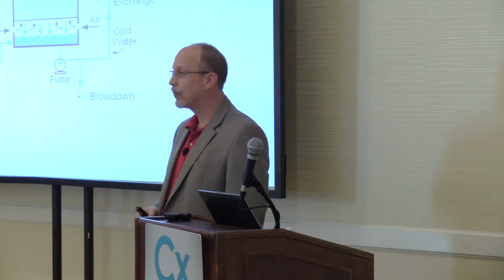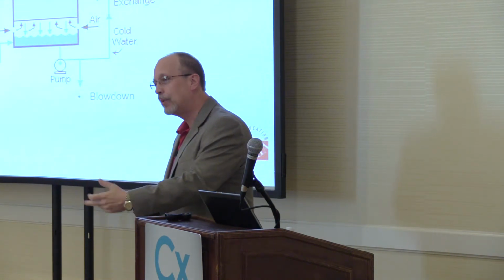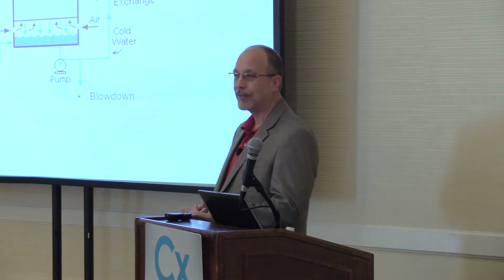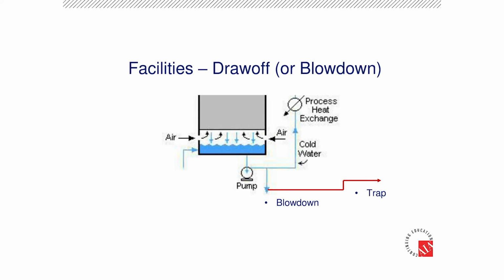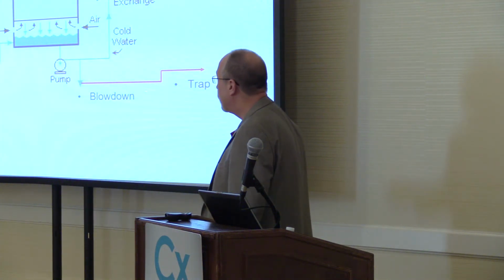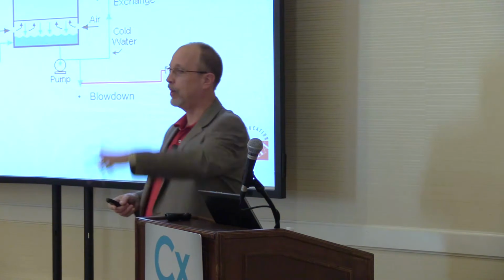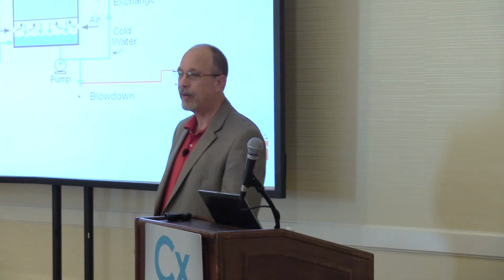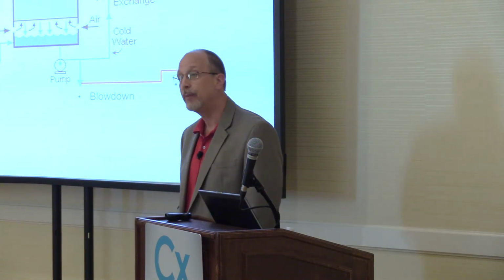So what do you do? I've done the exotic answer and the simple answer. The simple answer is put a trap in the line. You've got a full pipe. Once you put a trap in the line, just like under your sink, raise a little end there, you still have enough head pressure to push it through. You have a full pipe then over here. So when you have a full pipe, you can put an ultrasonic flow meter there, you can put a paddle wheel flow meter, you can put a city meter there, you can put a mag meter there, you can put all kinds of meters there.